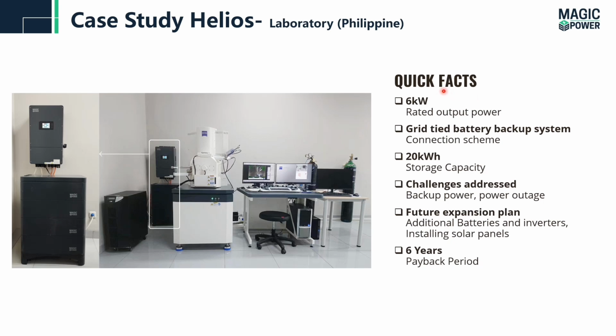If we look at the quick facts, the rated output power for the system is 6 kilowatt. Basically, the system is a grid-tied battery backup system at this stage because the solar panels are not connected to the system. The storage capacity is 20 kilowatt hours. The challenge addressed for the customer before installing the system was backup power. They require stable backup power, and there are a lot of power outages in that area.